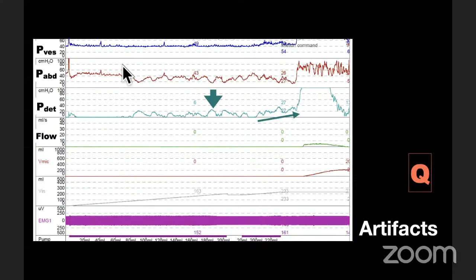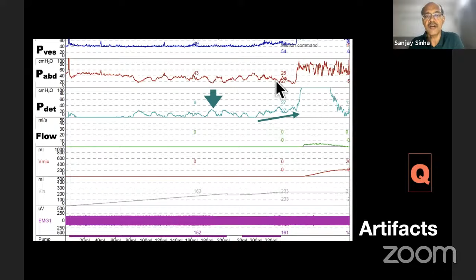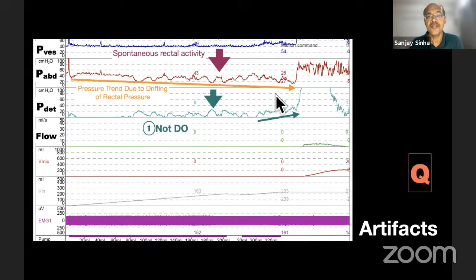So overall, the pressure in the abdominal channel has been dropping. And you can see that the vesical channel is holding steady. You can see the vesical channel at this point as well as at this point is more or less the same. But the pressure seems to be going up mostly because of a drop in the abdominal pressure channel. So spontaneous rectal activity is not detrusor overactivity. And there's a pressure trend because of drifting down of the abdominal pressure, which is contributing to what appears to be a poorly compliant bladder.